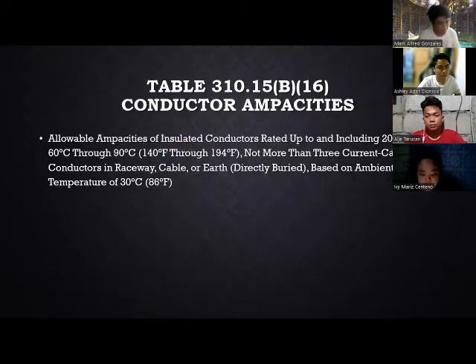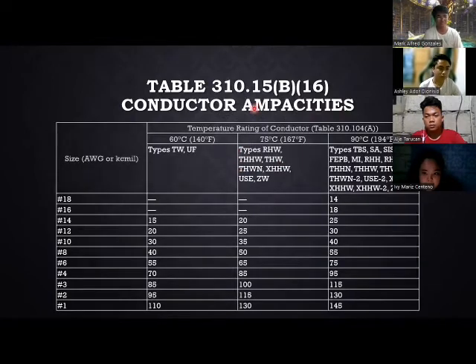Next, punta naman tayo sa mga tables na gagamitin for the wire sizing computations. First table is the table 310.15(B)(16), or the allowable ampacities for insulated conductors rated up to and including 2000 volts, 60 degrees to 90 degrees. Basta yan, mahaba na yan, is for the conductor capacities. For example natin, sabihin natin na size 10. Sa size 10 in 60 degrees na ginagamit doon ay TW or UF, ang capacity niya lang ay 30 amperes. Sa 75 degrees, 35. Sa 90 degrees, 40. Ganun lang.